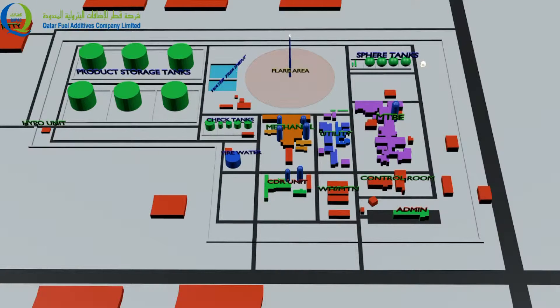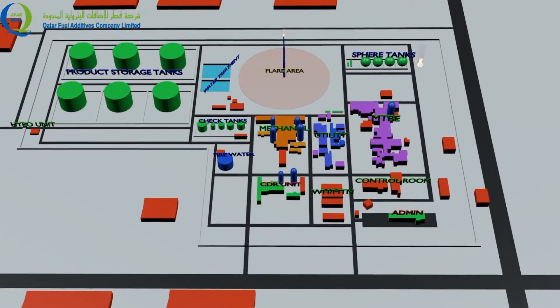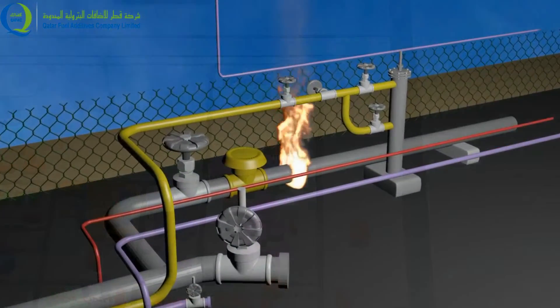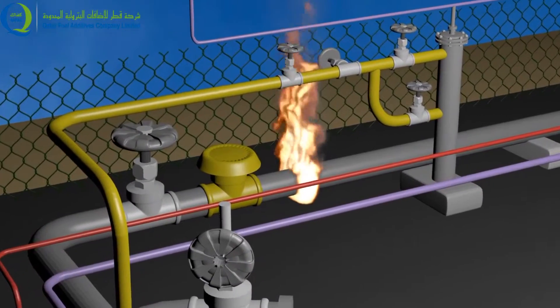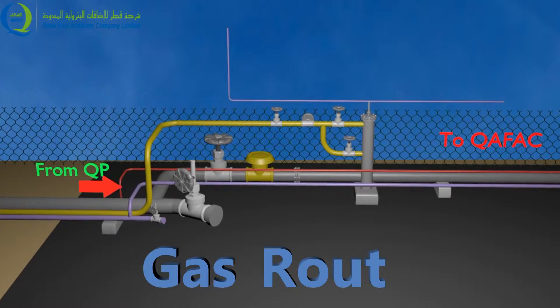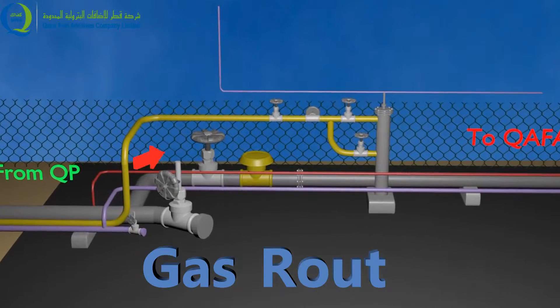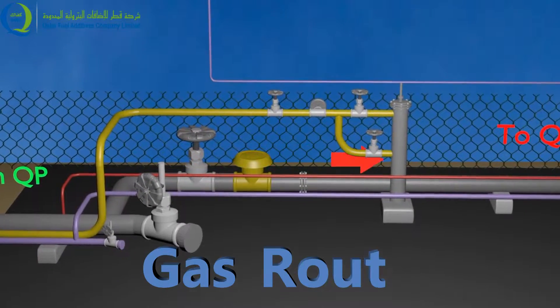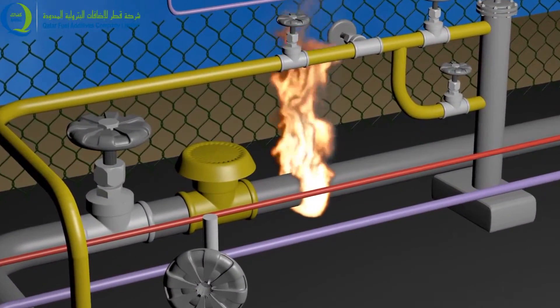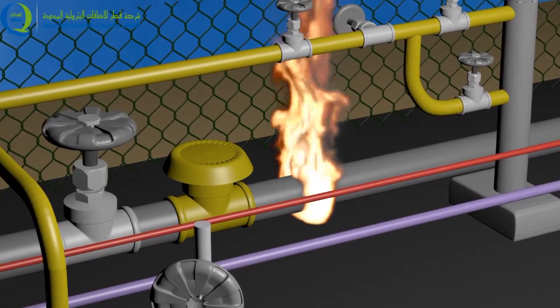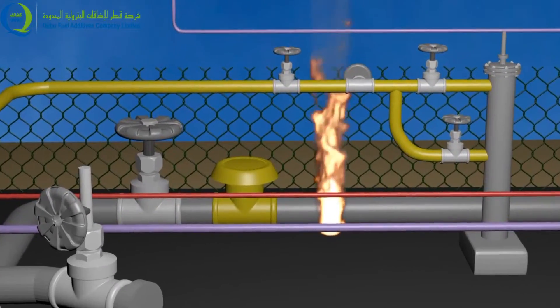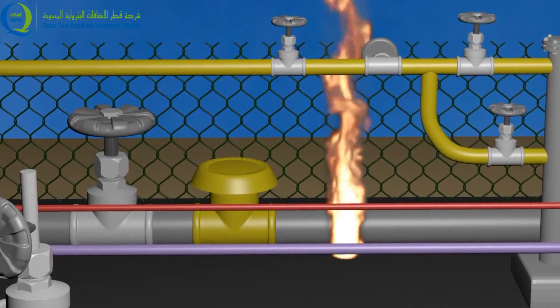This pre-planned scenario is a pressurized gas fire through a flange. Loss of containment of hydrocarbon gas occurred due to failure of a flange gasket in the gas receiving area. The gas route is from QP to QAFAC. The gas line has a 14-inch diameter and is at about 22 bar pressure. As gas continues to escape, fire is spreading to affect the installation and other gas lines in this area.